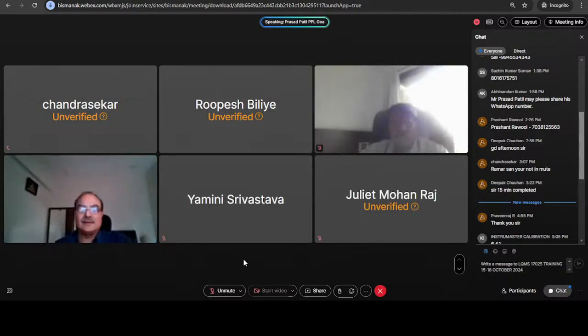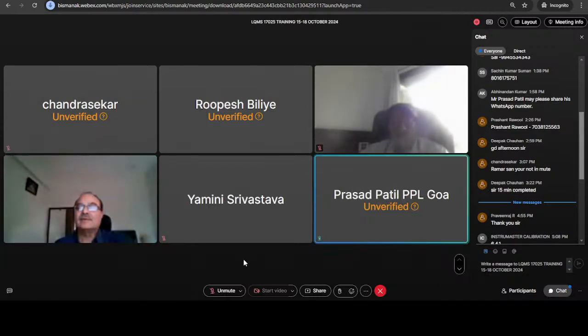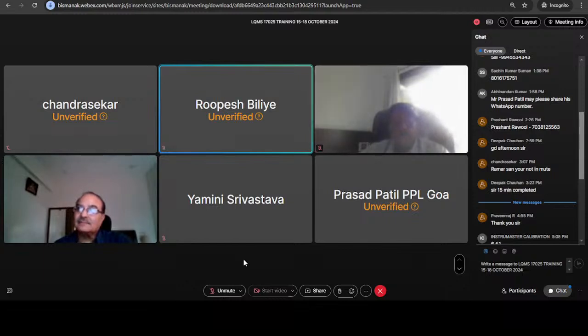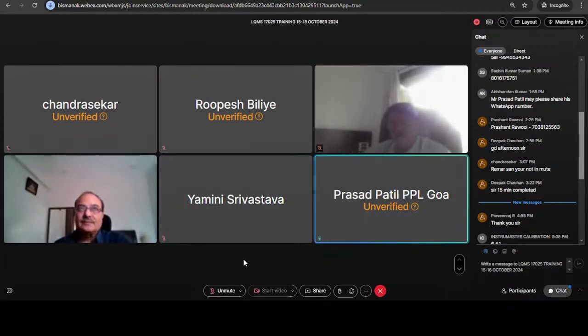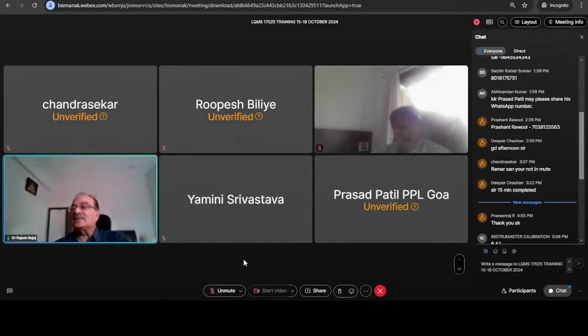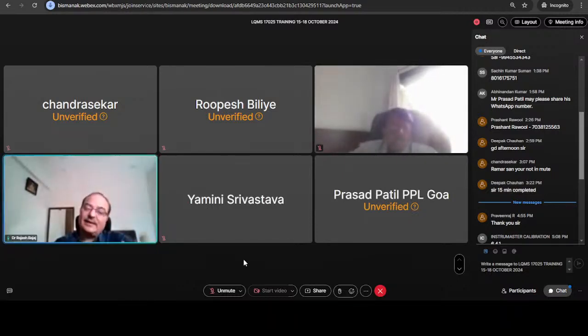Actually, how to close these LCs, sir? For example, any person is mishandling the balance, a 2 kg capacity balance is handling 5 kg. How to close this type of LC? You have to close that in the sense that you have to take it away, label it, get it calibrated, and start using it again.